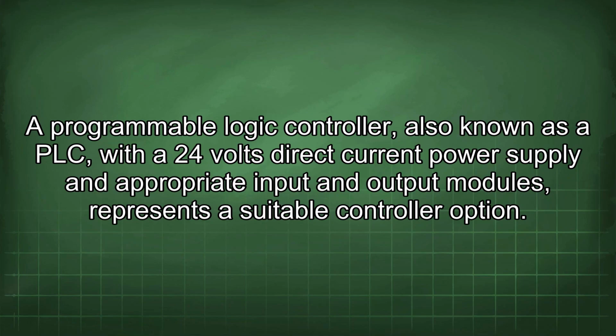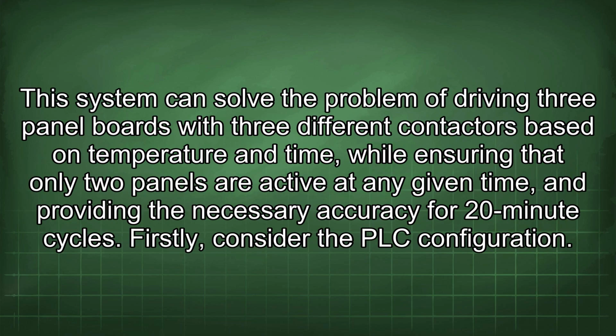A programmable logic controller, also known as a PLC, with a 24 volts direct current power supply and appropriate input and output modules, represents a suitable controller option. This system can solve the problem of driving 3-panel boards with 3 different contactors based on temperature and time, while ensuring that only 2 panels are active at any given time and providing the necessary accuracy for 20-minute cycles.